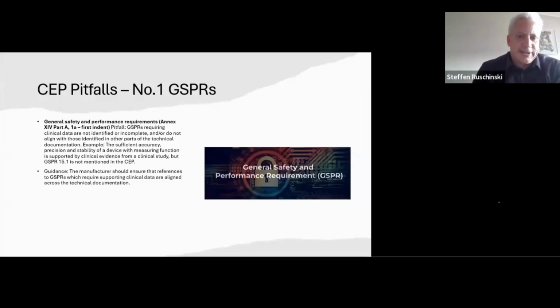Yeah, and first, for the CEP, what we have to do is determine our relevant GSPRs. A pitfall is that these GSPRs require clinical data, and this data is not identified, or is incomplete, or does not align with those identified in other parts of the technical documentation. For example, the sufficient accuracy, precision, and stability of a device with a measuring function is supported by clinical evidence from a clinical study, but we don't mention GSPR 15.1 in the CEP. So the manufacturer always has to ensure that all references to the GSPRs which require supporting clinical data are aligned across the whole technical documentation.